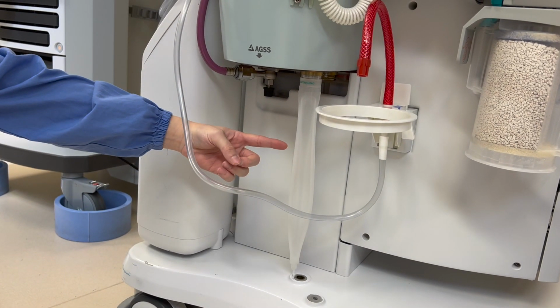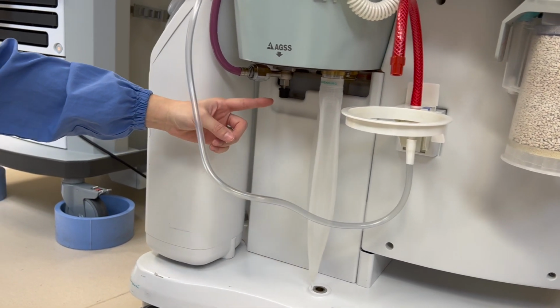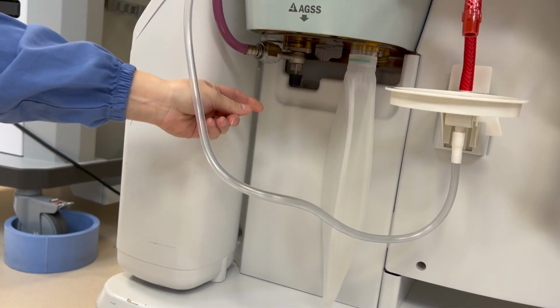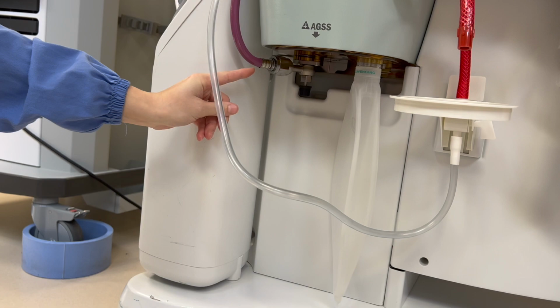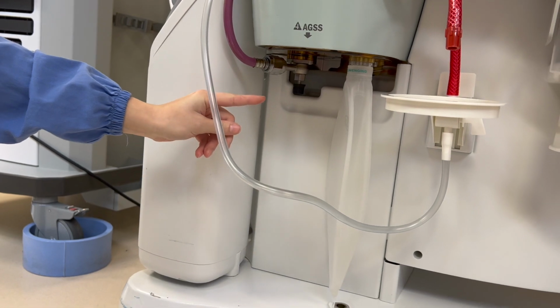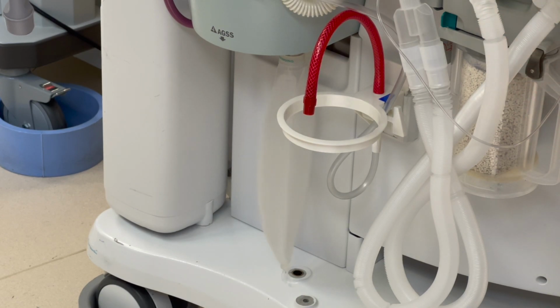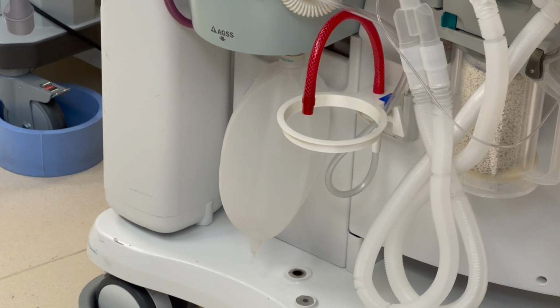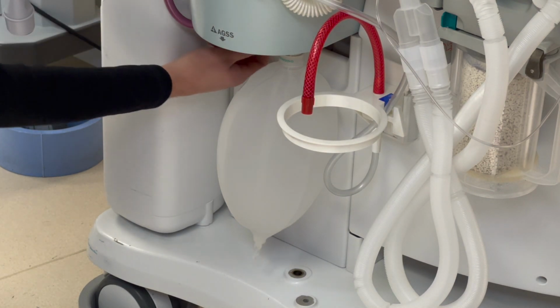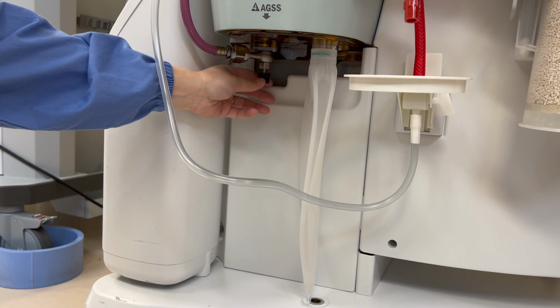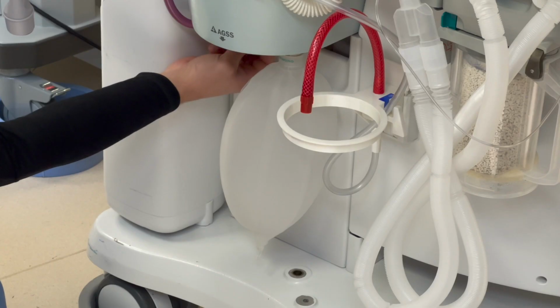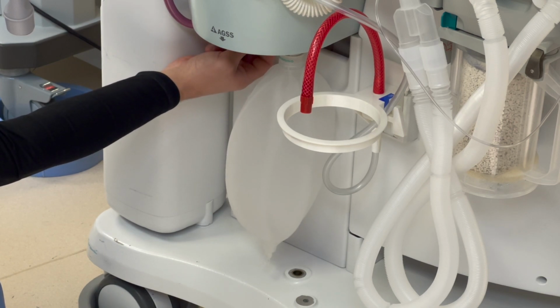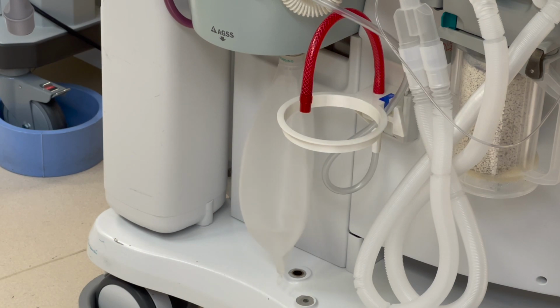You won't be expected to actually test the scavenging system bag, but you should know where it's located and what it looks like. This white bag here is your scavenging bag, and then the purple pipeline next to it is your anesthesia gas scavenging system, which will vacuum away the anesthetic waste gases. In the normal position, it'll be deflated, but if there's a problem, this bag will start to increase in size. If possible, call an anesthesia tech to come and check it with you. But if one's not immediately available, try reaching under and making sure that the valve is all the way open by adjusting this black cap. Once the vacuum has been restored, the bag should slowly decrease in size and shape and return to normal.